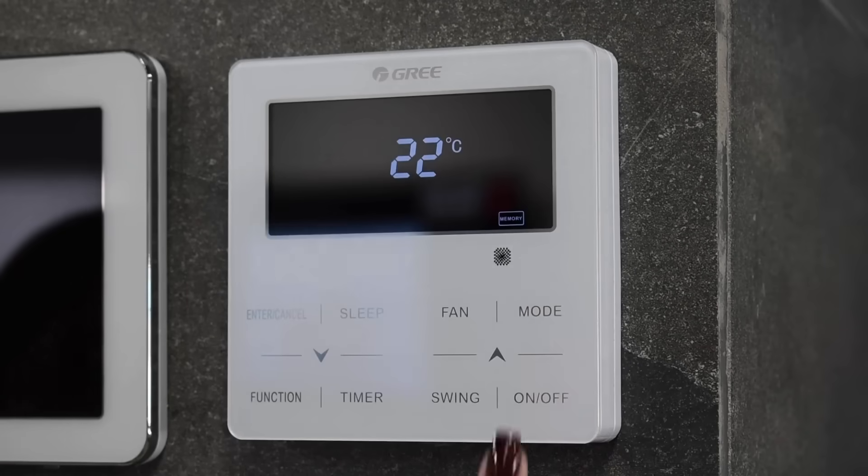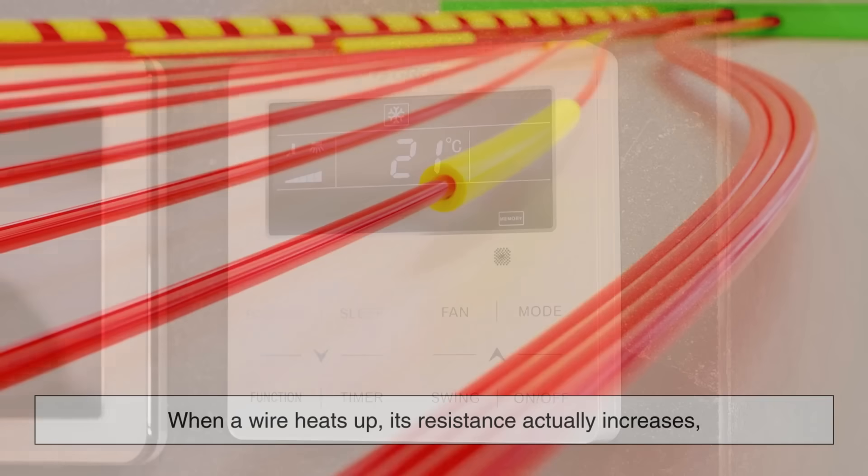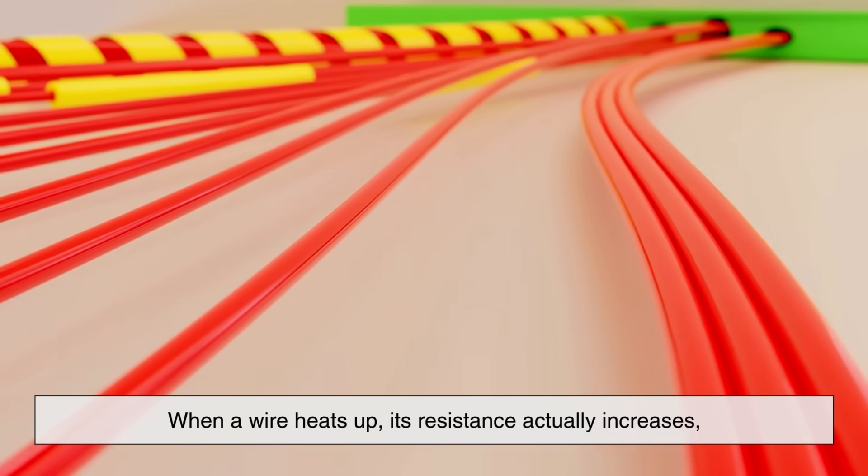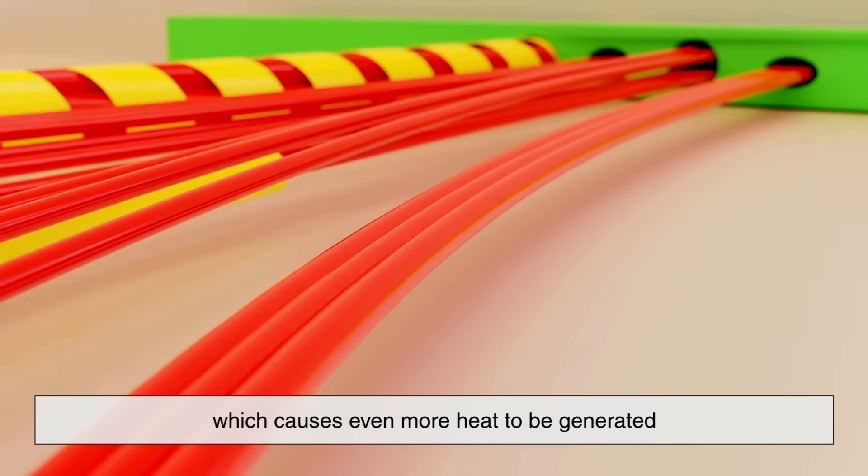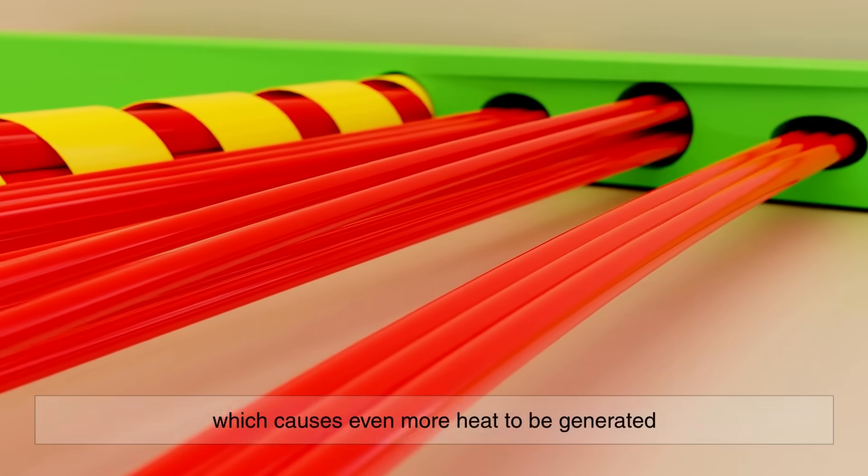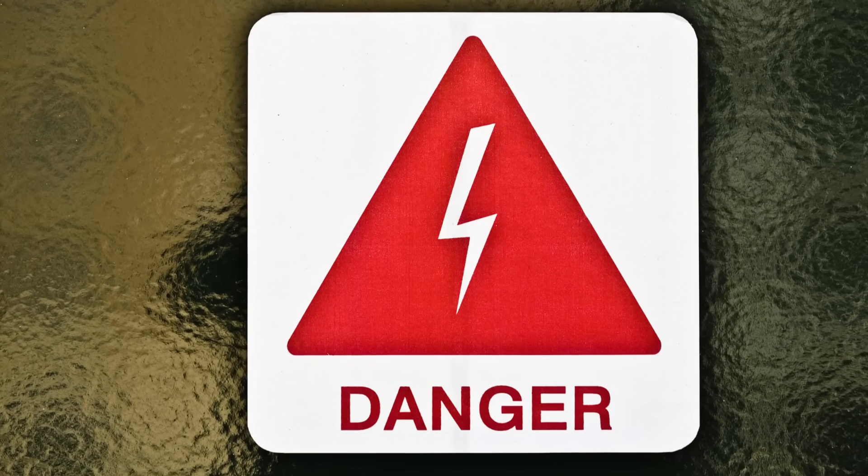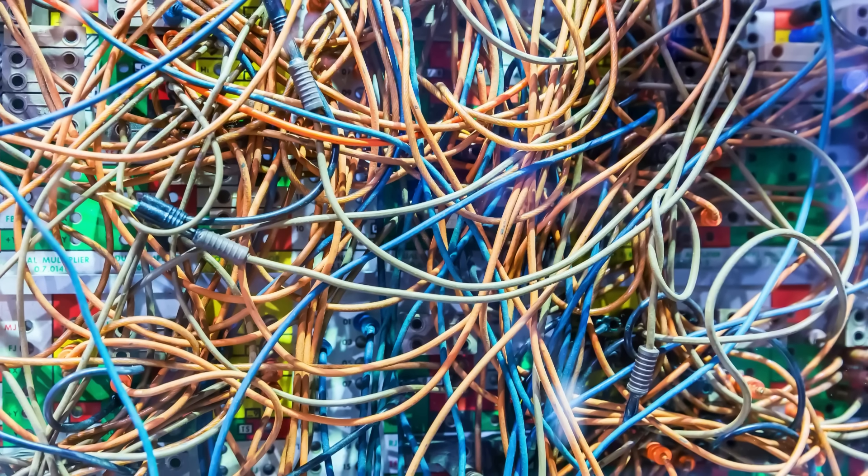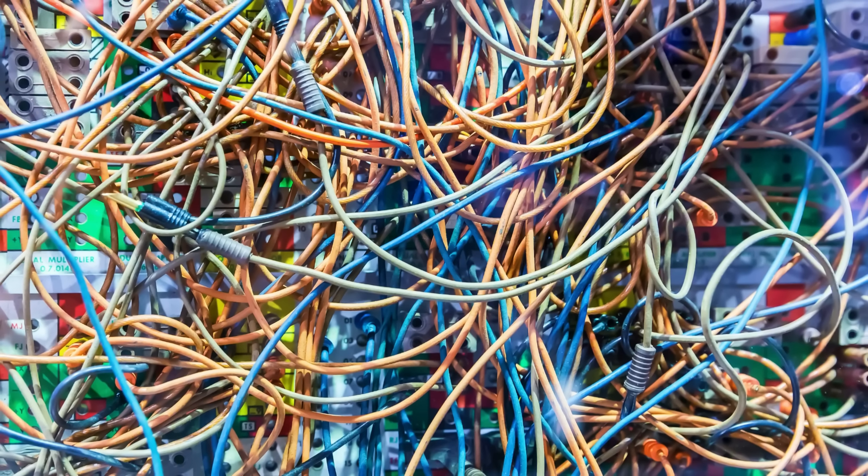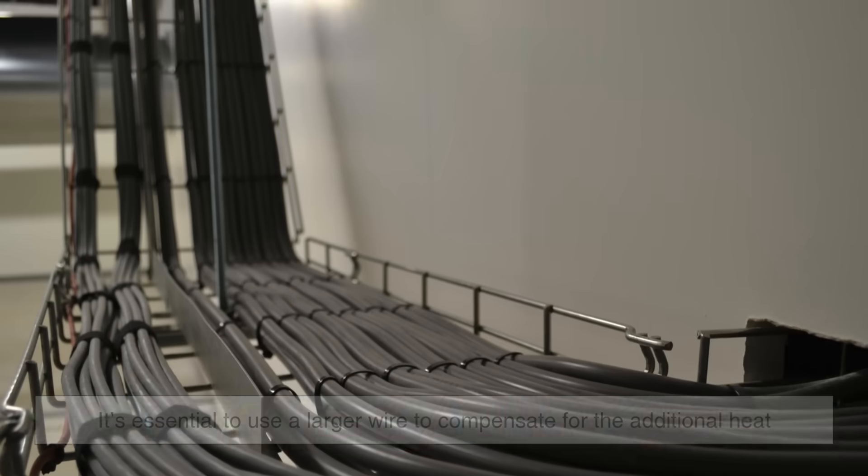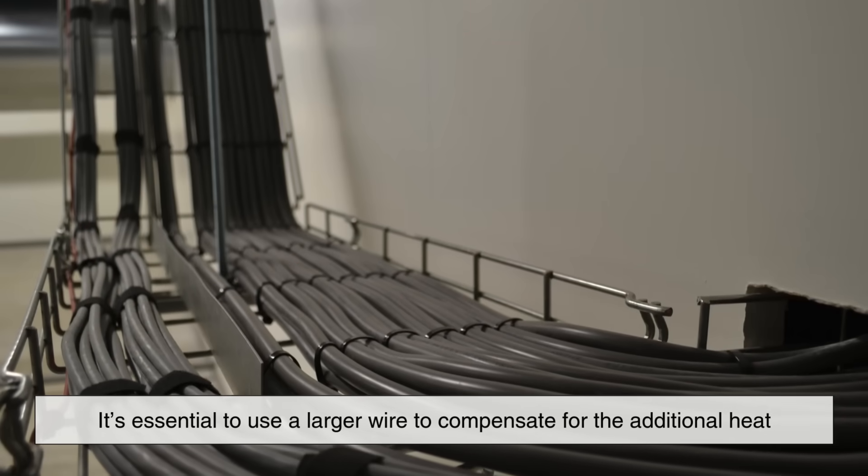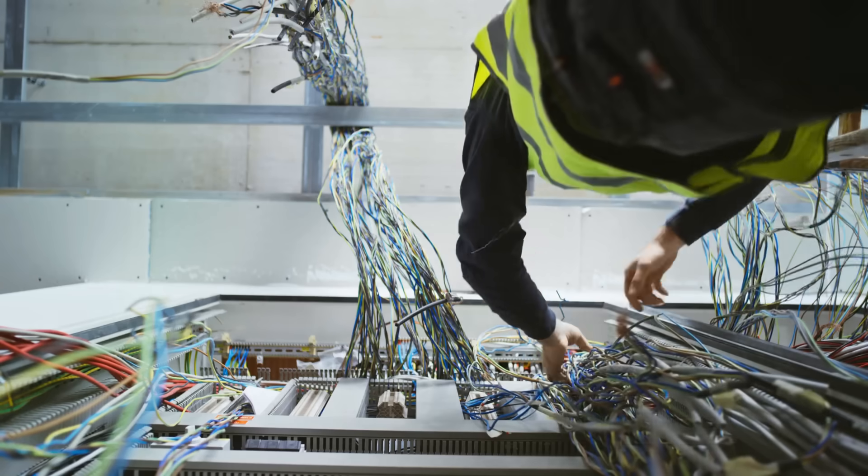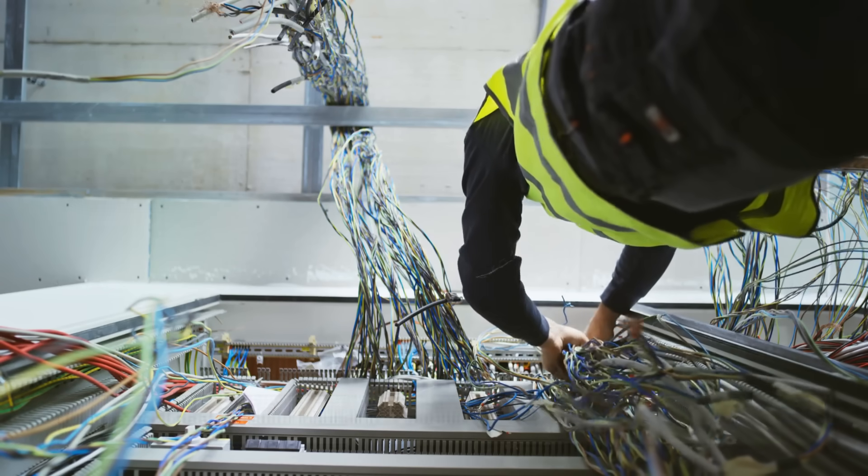Temperature is an interesting piece of this puzzle. When a wire heats up, its resistance actually increases, which causes even more heat to be generated—a dangerous cycle. In hot environments or in situations where wires are bundled together with little ventilation, it's essential to use a larger wire to compensate for the additional heat.